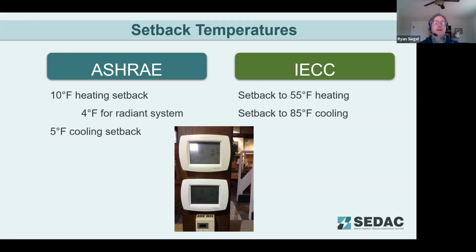IECC, however, requires the setback on the heating side to go back to 55 and the cooling to go up to 85. So that's rather dramatic setups and setbacks. If you figure your typical temperatures are perhaps going to be somewhere around 70 heating and 75 cooling, that's going to be like a 15-degree heating setback and a 10-degree cooling setback. So rather dramatic difference there.